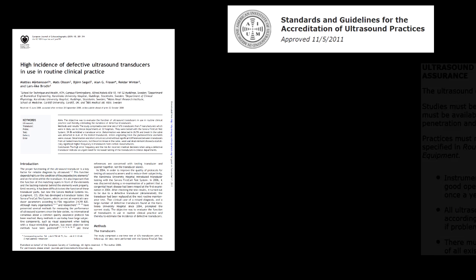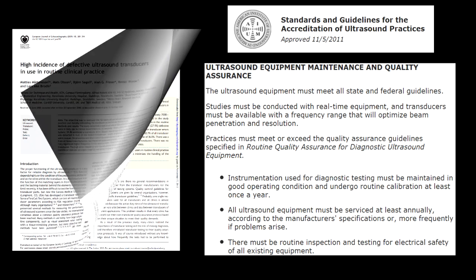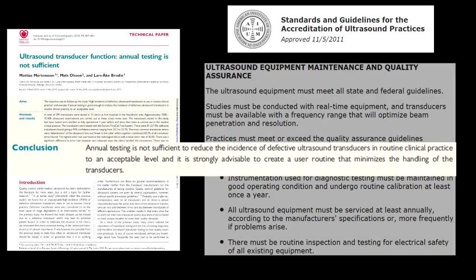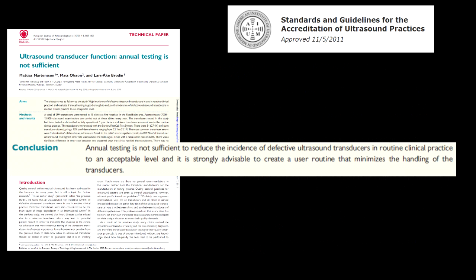The American Institute of Ultrasound in Medicine has attempted to combat this by requiring that equipment maintenance be performed at least once a year in order to keep one's AIUM accreditation. However, follow-up research on this study suggests that even annual maintenance is not enough to ensure that an acceptable number of transducers are working properly. Further, AIUM accreditation is not required to practice sonography in the first place.